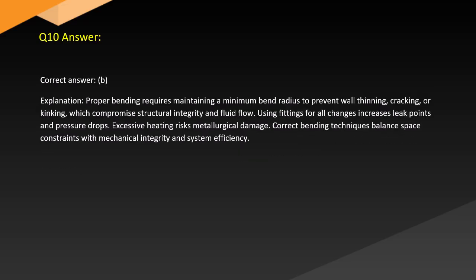Answer. Correct answer. B. Explanation. Proper bending requires maintaining a minimum bend radius to prevent wall thinning, cracking, or kinking, which compromise structural integrity and fluid flow. Using fittings for all changes increases leak points and pressure drops. Excessive heating risks metallurgical damage. Correct bending techniques balance space constraints with mechanical integrity and system efficiency.